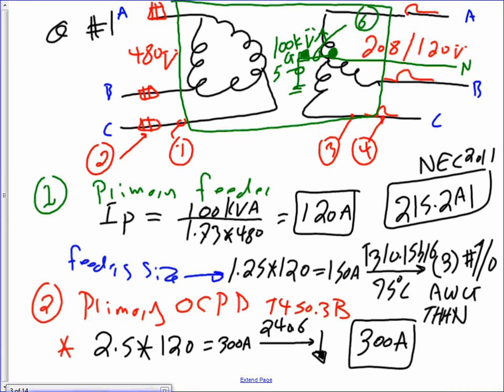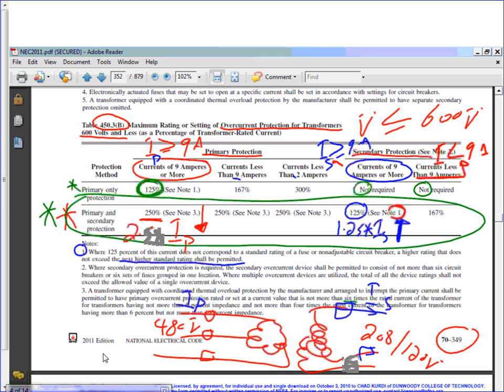One more time. You multiply your full load current by 2.5. It gives you 300 amp. 300 amp is a standard. How do I know? Take it to 240.6, and that will get you a 300 amp as a standard. If it was 305, Derek, what do you do? You go down to 300. See that little arrow here? That's your indication that you're going down. Why do you go down? Because, gentlemen, this is the primary. It doesn't say go up. It doesn't have note number 1 next to it.